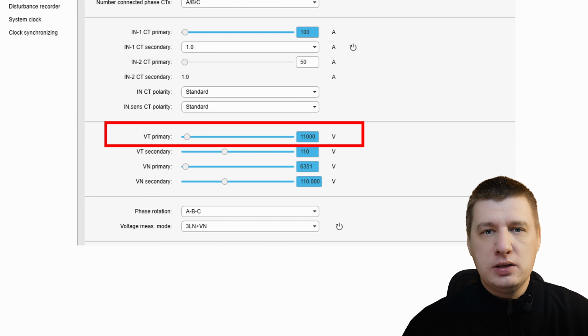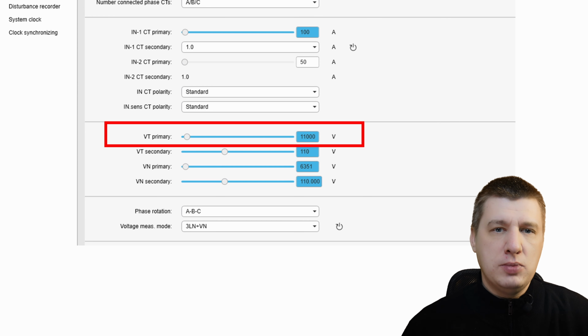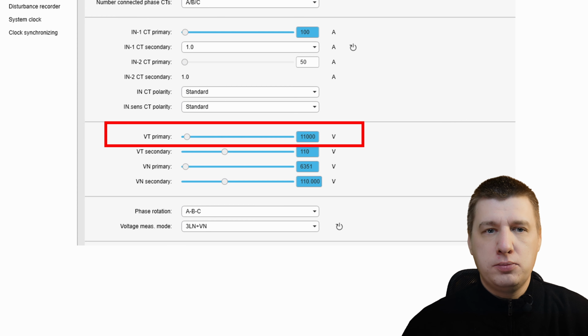You can configure the VT primary anywhere from 75 volts all the way to 500,000 volts. This allows the same relay to be used in every form of low voltage industry site up to massive high voltage substations. To set this up, open Pro setboard, navigate to the General menu and select the scaling view. You see the field for VT primary right there. Make sure this matches the primary nameplate rating of your VT exactly.